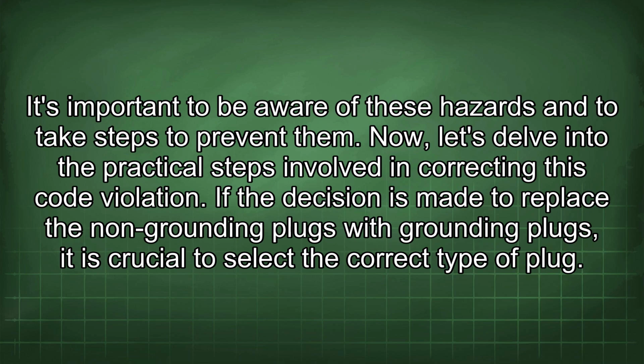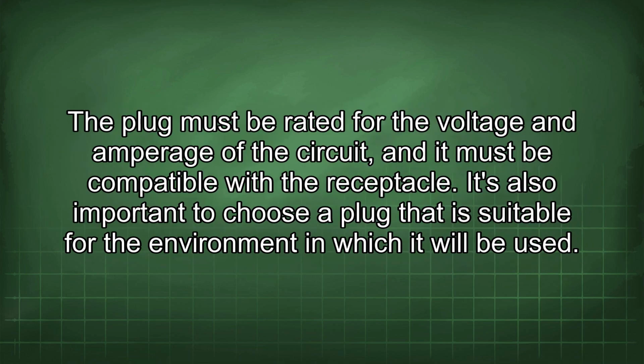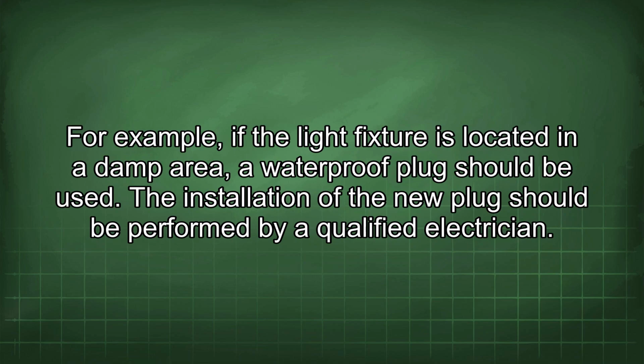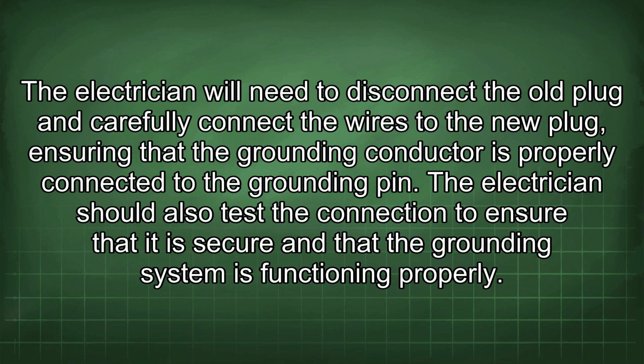If the decision is made to replace the non-grounding plugs with grounding plugs, it is crucial to select the correct type of plug. The plug must be rated for the voltage and amperage of the circuit, and it must be compatible with the receptacle. It's also important to choose a plug that is suitable for the environment in which it will be used. For example, if the light fixture is located in a damp area, a waterproof plug should be used. The installation of the new plug should be performed by a qualified electrician. The electrician will need to disconnect the old plug and carefully connect the wires to the new plug, ensuring that the grounding conductor is properly connected to the grounding pin.